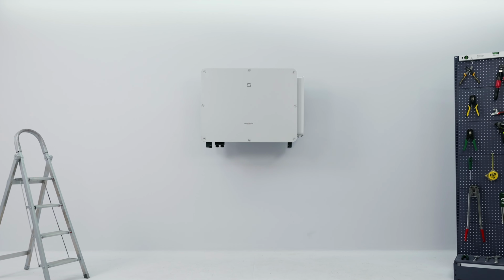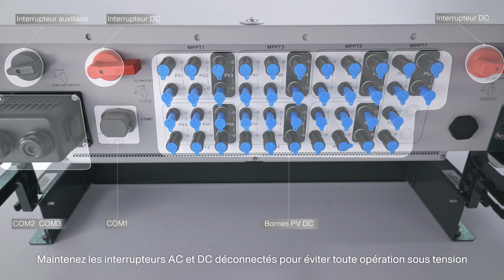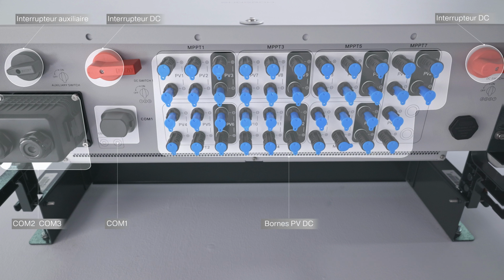Step 3. Electrical connection. Keep both the AC and DC switches disconnected to avoid live line operation. 1. Crimp OT or DT terminal. Place the heat shrink or cold shrink tubing over the cable. Connect the terminal to the cable and secure it with a hydraulic pliers. Use a heat gun to tighten the heat shrink tube or cold shrink tube.